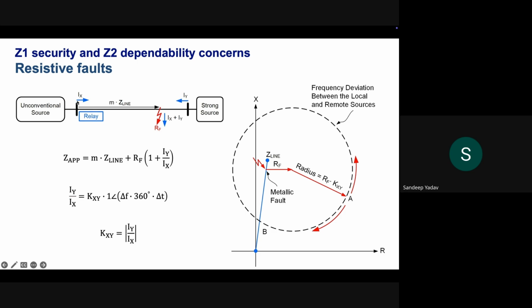So there is a line between terminals X and Y. Y is the strong source, which is nothing but a lot of synchronous generators acting in parallel, and X is the current contribution from an unconventional source, which is solar PV or wind or battery energy storage. So for a relay located at the X terminal, the apparent impedance seen into the line would be M into Z line. M is nothing but the location of the fault. So if the fault is at, say, 50%, M becomes 0.5.